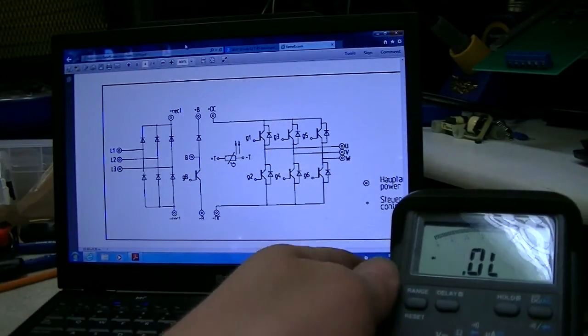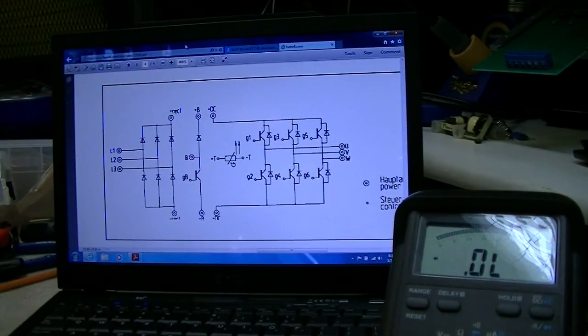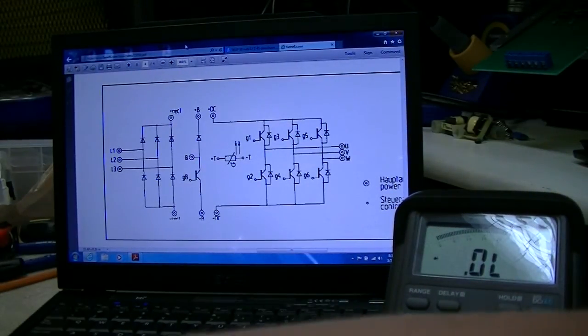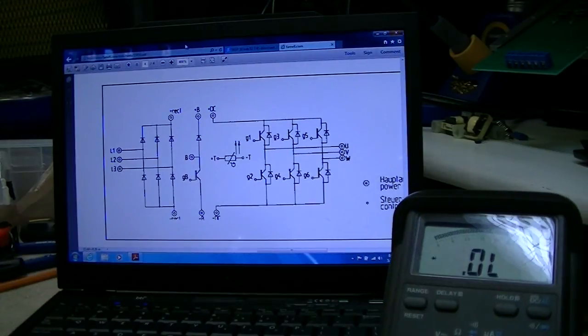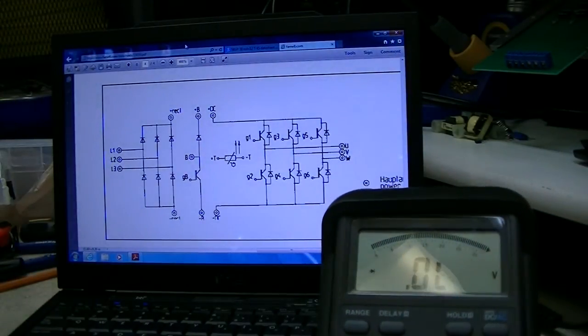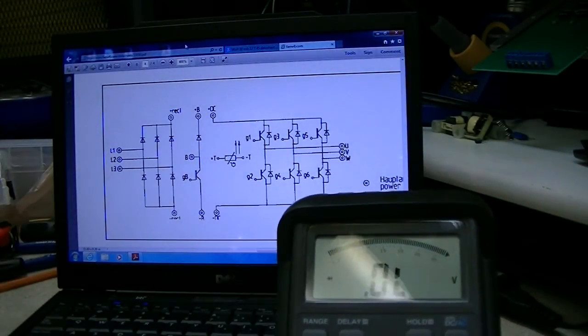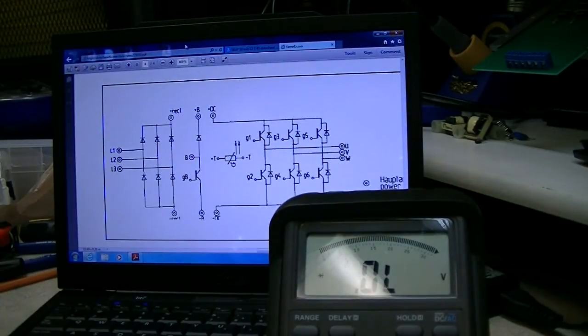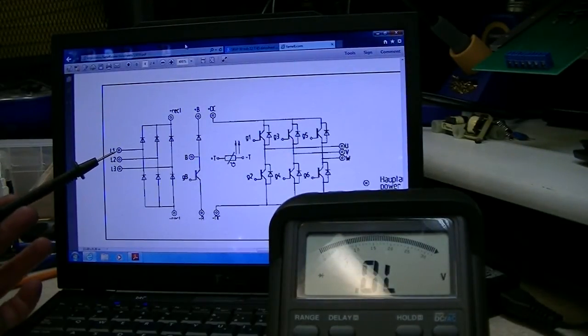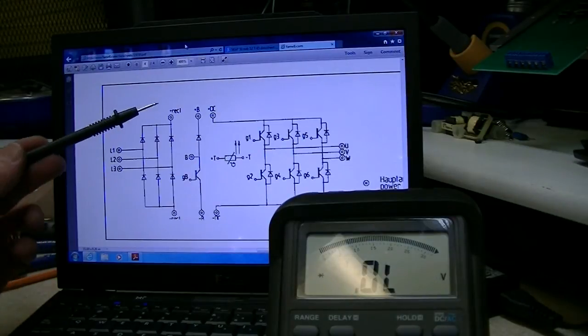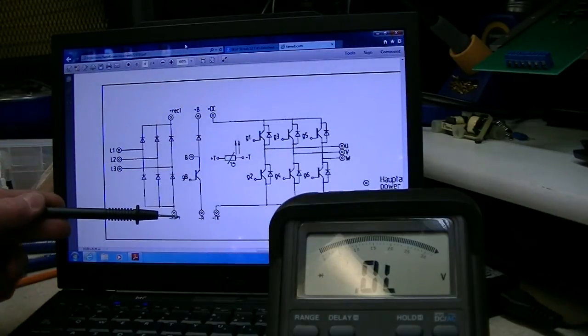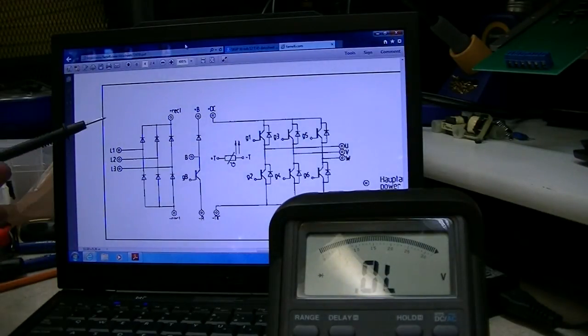And I've got my meter on the diode function. I'll try to kind of get all this in here together at the same time. Right now what I'm doing is testing this right here, the L1, L2, L3. This is the bridge rectifier section right here of this IGBT.